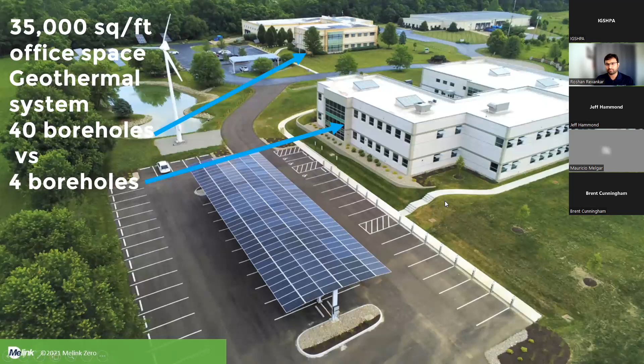Our pumping package that I've briefly talked about, we call it the manifest system. It's got Armstrong pumps, all of it built into a skid with expansion, thermal expansion, and storage and all that, and air separators. The 2 pipes going into the ground go to the bore field, which is connected to 4 boreholes. Again, 4 boreholes for this entire building.